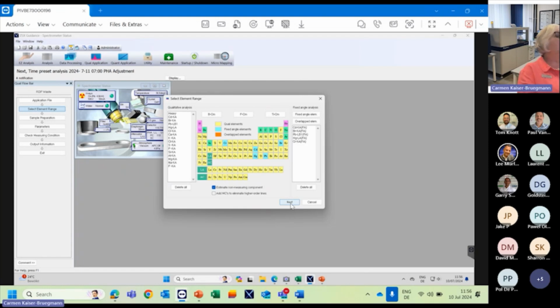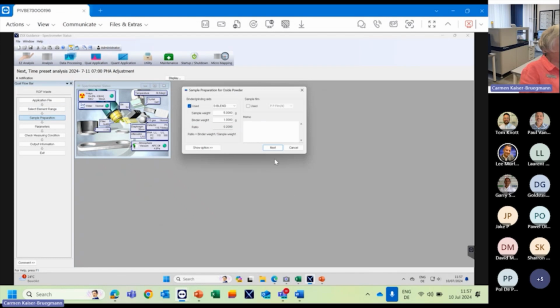This is also a very nice feature in our software. We can get better counting statistics for trace elements, for example, and we can look at mercury or cadmium for a longer period and count longer on the background. We also have the possibility to estimate the non-measured components because it's waste. Waste is predominantly organic material with a lot of plastics and so on, so we can measure the Compton line to estimate the balance of the material. You can include the preparation of your sample, so there is a lot of traceability within the methods.